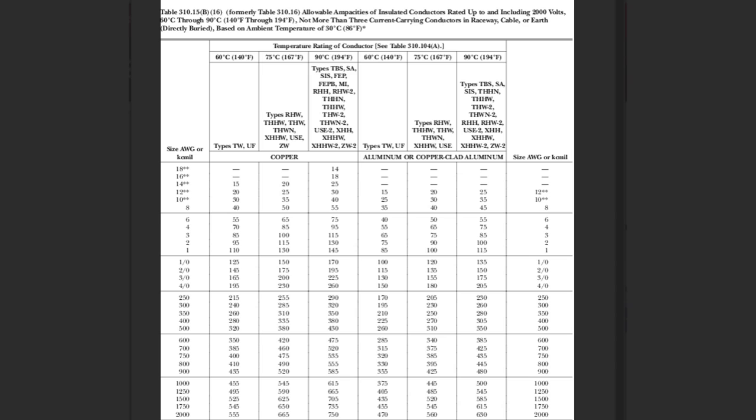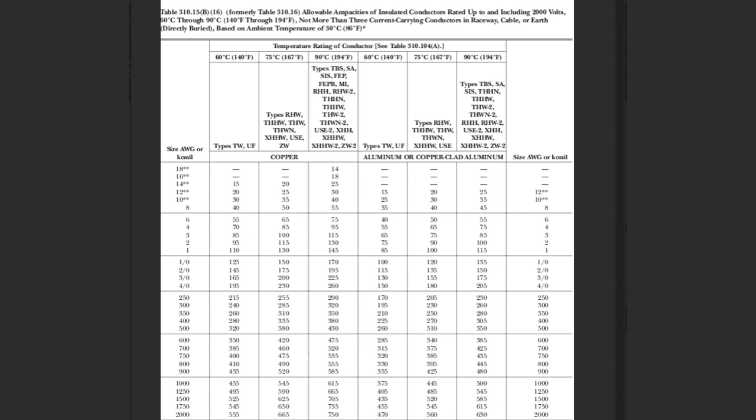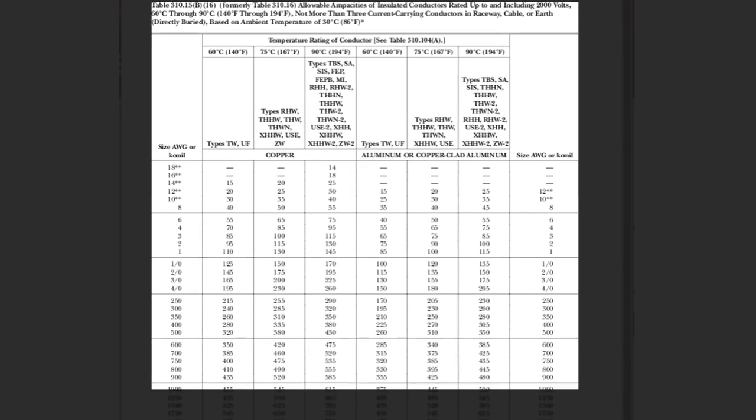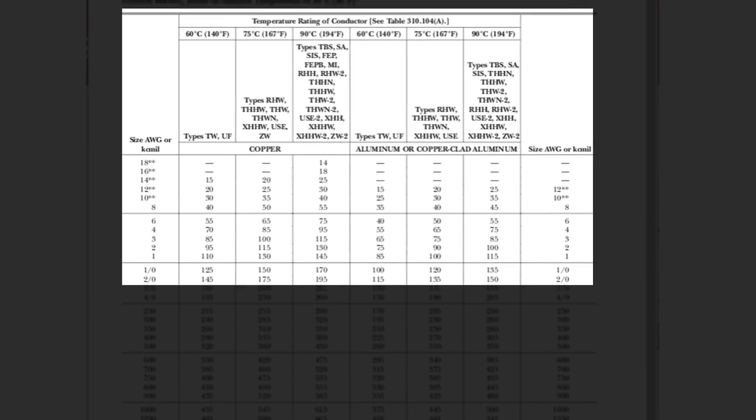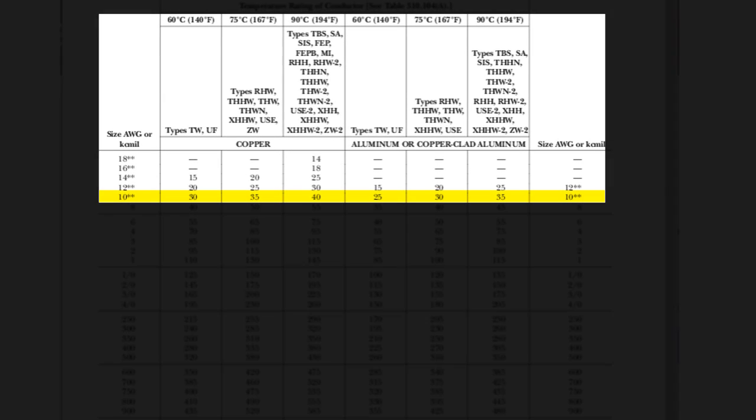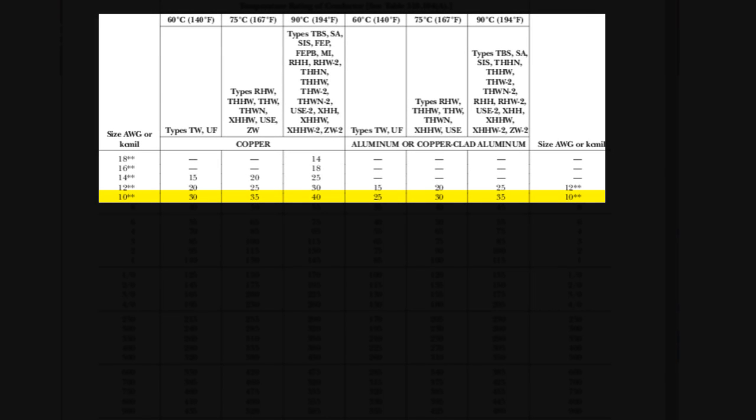If you go to 310.15b16, this gives you the actual temperature rating of different conductors and the sizes, the ampacities that can be run on those conductors. As an example, we'll use a common one, we'll look at number 10 wire. Number 10 wire at 60 degrees Celsius, which is 140 degrees Fahrenheit insulation rating, is rated at 30 amps. So that's what we typically hear. We hear number 10 is 30 amps period, right?